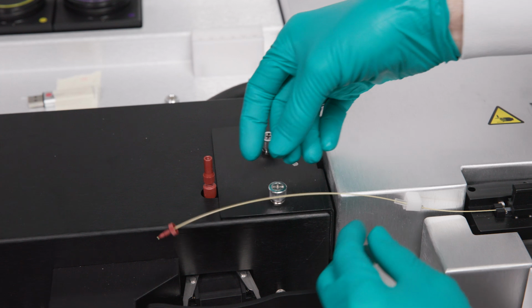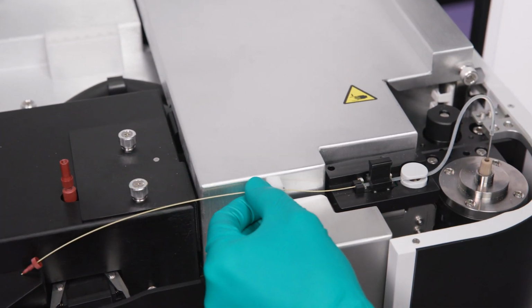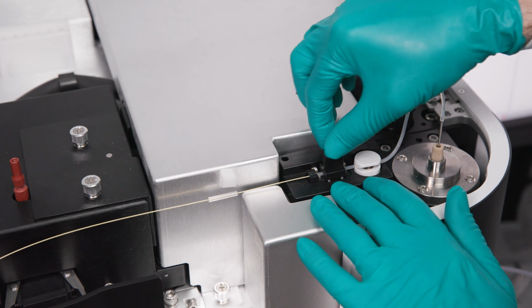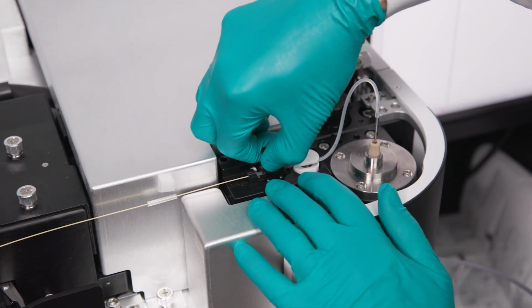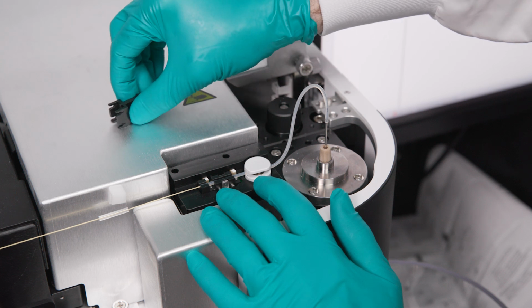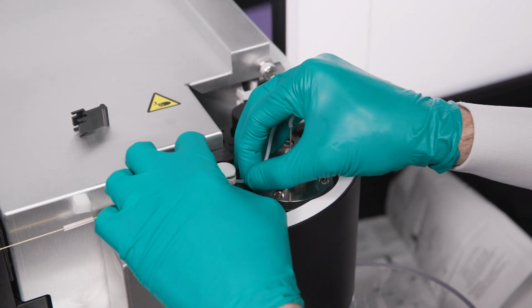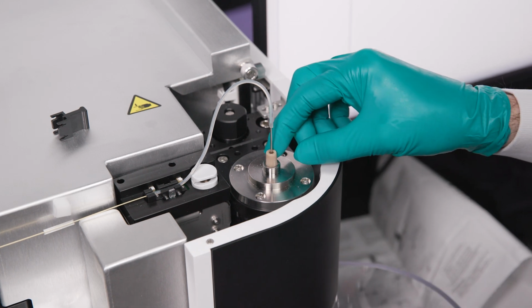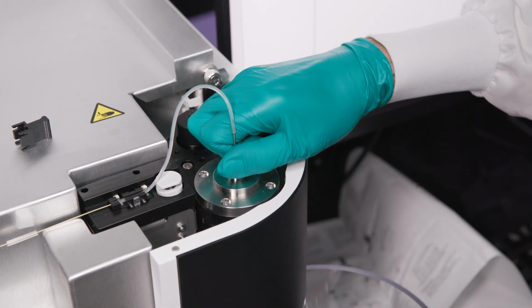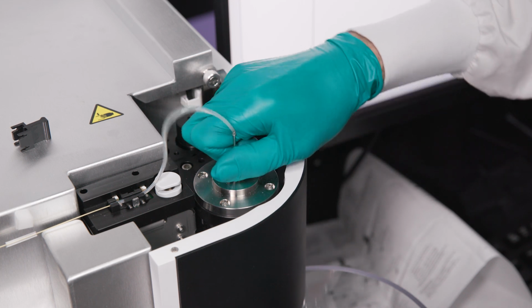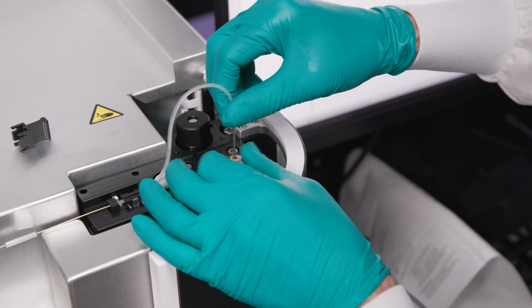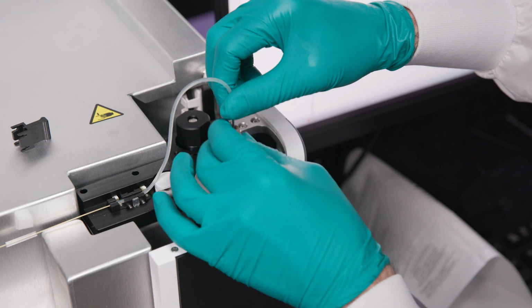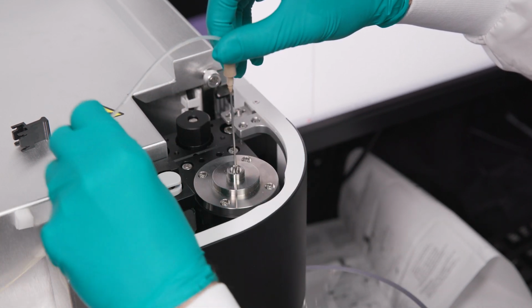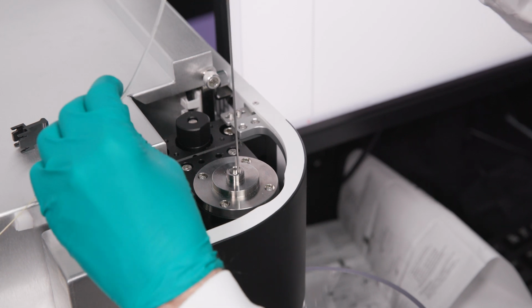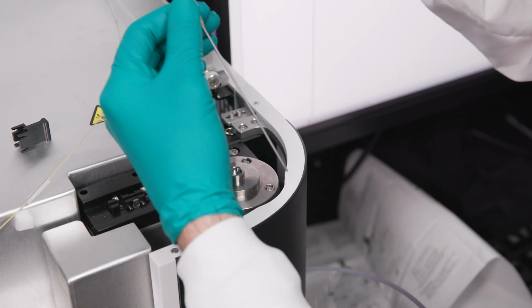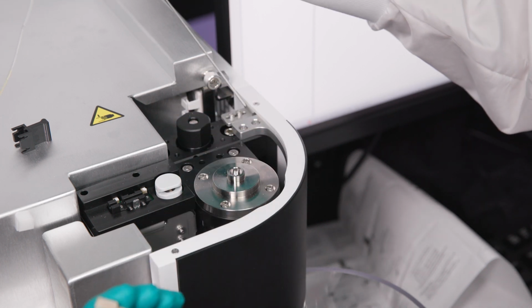So that part removes. You can then remove it from this guide. Remove the cover to the bubble detector. And then remove the tubing from the pinch valve. And then we have a finger tight connection here for the sample probe itself, which once it's loosened, the probe will come free, and can be removed from its screw.